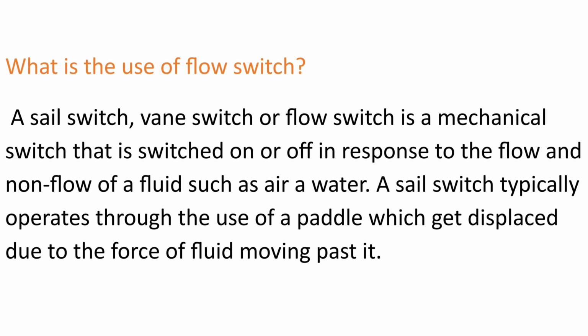What is the use of a flow switch? A sail switch, vane switch or flow switch is a mechanical switch that is switched on or off in response to the flow and non-flow of a fluid such as air or water. A sail switch typically operates through the use of a paddle which gets displaced due to the force of fluid moving past it.